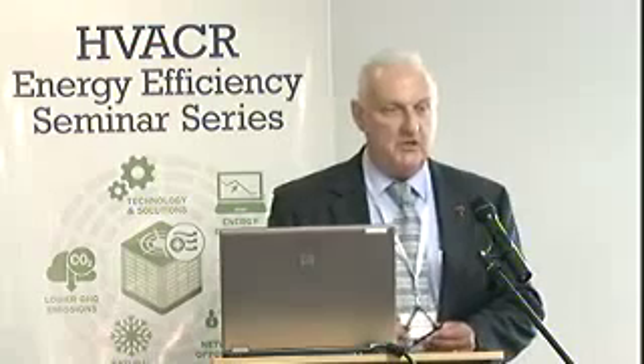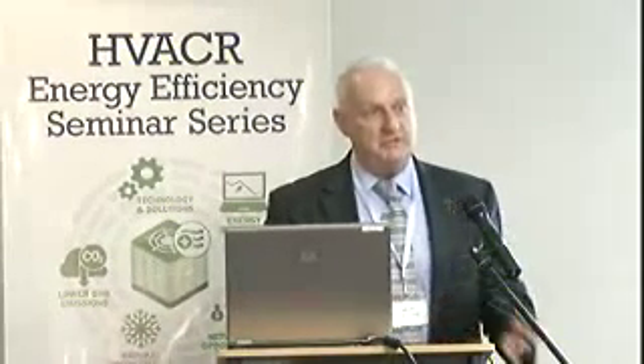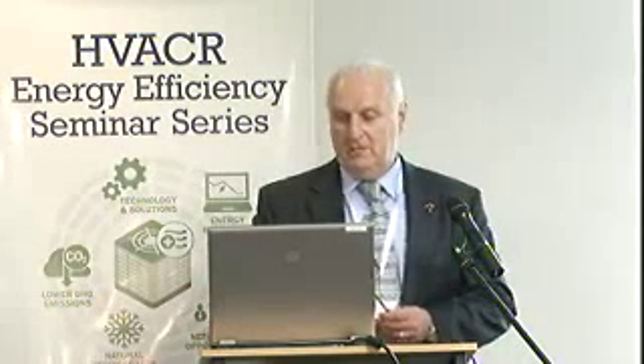In reality, manufacturers of the equipment that you use actually design for that. So if you go to the NEMA website, you'll find they talk about motors, for instance, being designed for plus or minus 10% of the nameplate voltage to operate normally. Doesn't necessarily mean that's optimum though.